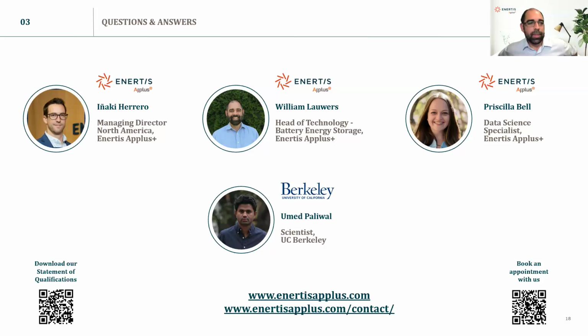Sure, there can be a few potential implications there. The models could show potential harmonics and interplay between the storage and the existing generation. Typically, that's more of a concern for new storage sited close to an existing thermal peaker, or a new interconnection right next door in the same substation. Because of the opportunity I was talking about earlier, since they're behind the same MPT, they would generally have a relay, so it's either the thermal plant or the storage operating at any given time. You're not going to find that harmonic issue because they won't operate at the same time.